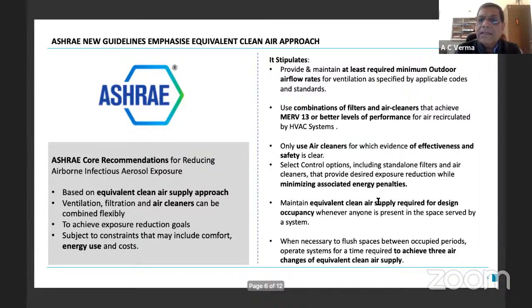And there are a few guidelines here: provide and maintain at least the required minimum outdoor airflow rates. Then it talks about combinations of filters and air cleaners to achieve MERV 13, that is the filtration effectiveness level 13. Presently we have 6 or 8. Now it has to be increased to MERV 13 for a better level of performance. And only use air cleaners for which evidence of effectiveness and safety is clear.